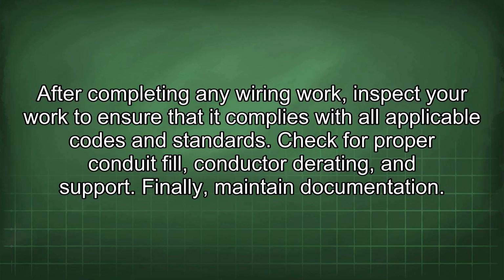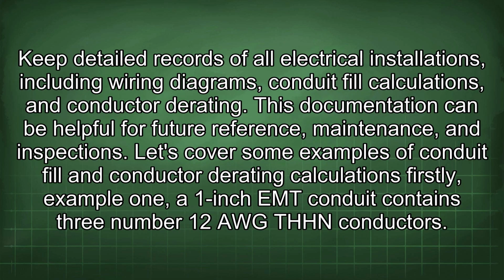Check for proper conduit fill, conductor derating, and support. Finally, maintain documentation. Keep detailed records of all electrical installations, including wiring diagrams, conduit fill calculations, and conductor derating. This documentation can be helpful for future reference, maintenance, and inspections. Let's cover some examples of conduit fill and conductor derating calculations.